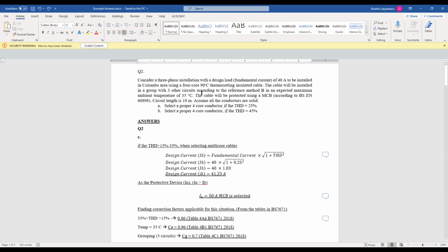So we'll start the question. Here it says there's a three-phase installation, and the design current, actually the fundamental current, you have found to be 40 amperes, and this is installed in the Colombo area, and you are going to use 4-core thermosetting insulated cables. The most important term here is 4-core. That means the whole circuit is fed by a single cable with 4 cores. Therefore, when we size multiple core cables, we have to consider many things, because all the cores are equal to each other.